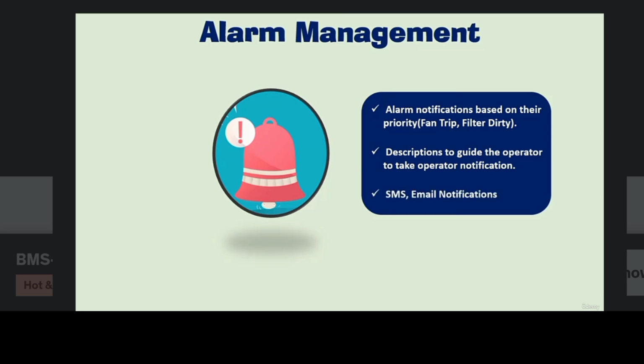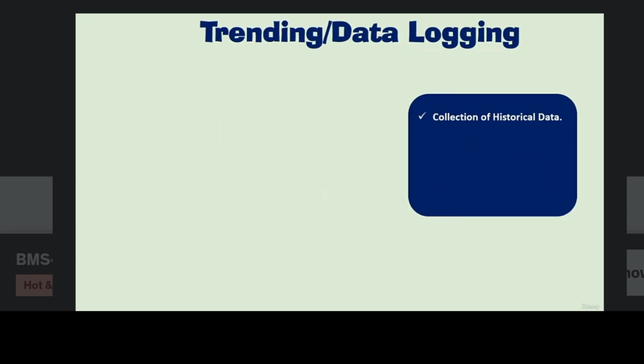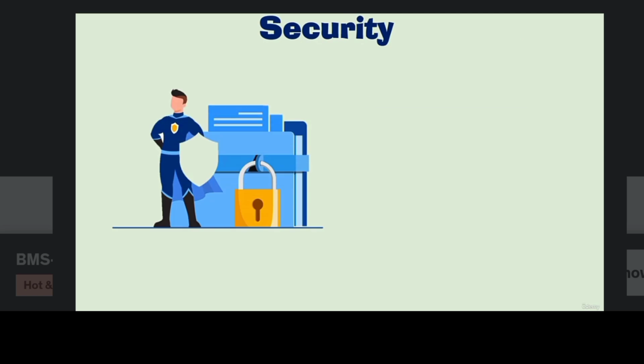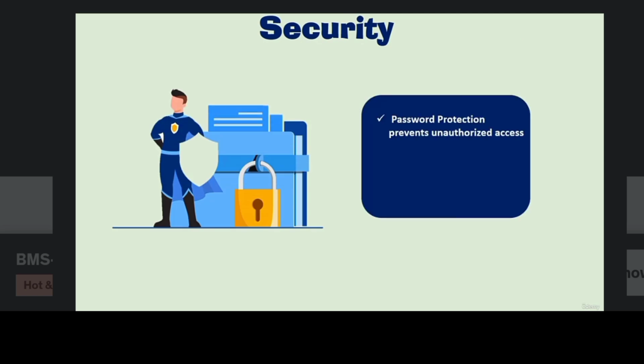Different instructions can also be set which will guide the operator to take appropriate actions for different alarms. Alarms can also be notified using SMS and email notifications. Trending is an automatic gathering and storage of historical data from field equipment. It helps in troubleshooting and later analysis. BMS also prevents unauthorized access to the system using password protection. Also, we can define different roles for different operators to limit their access, meaning operator will be able to only access specific area and functions for which he is authorized. Operator log summary is also available in the BMS, which can be referred to later on to know which actions were taken by which operator.